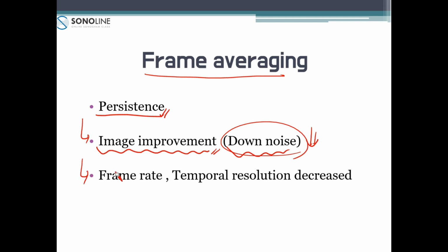On the other hand, if you look at the drawbacks, since it takes longer to create each frame, the temporal resolution and frame rate decrease accordingly. It takes a long time, and similarly, creating a single image also requires a significant amount of time. Please keep that in mind. I think you just need to pay attention to these two factors that you can gain through this technique. I can explain that the most notable feature of this technique is that while image quality improves and noise decreases, the frame rate and temporal resolution are reduced.